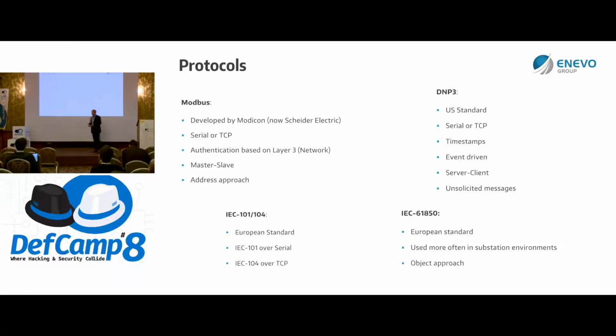Protocols. In the industrial control area you don't see the general enterprise protocols. You see protocols dedicated to carrying data from the field, from the PLCs, and sending it upstream. You have Modbus, one of the first industrial protocols, developed by Modicon. It's serial and TCP, and it's a master-slave system, so we're still in the area of master-slave here.